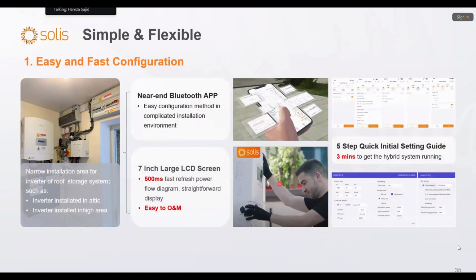Easy and fast configuration. The best way is if you install the system somewhere, you can easily set it up from the Bluetooth app or from the screen. We have a 7-inch large LCD screen with 500 millisecond fast refresh. So you can see all the power flow directly on the screen. Mostly the end users are worried about how much power we make, how much we discharge, and what the instantaneous power moving right now is. You can see all these things, and you can easily see any error that comes up, or whether the inverter is working according to your requirement.